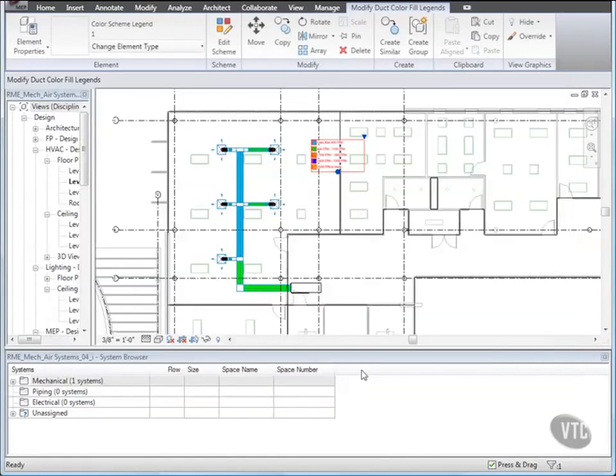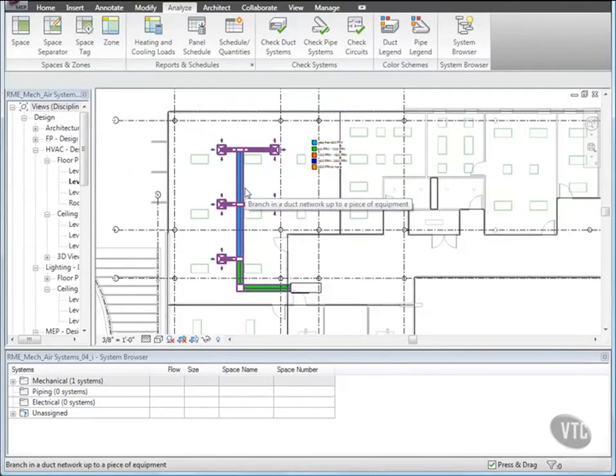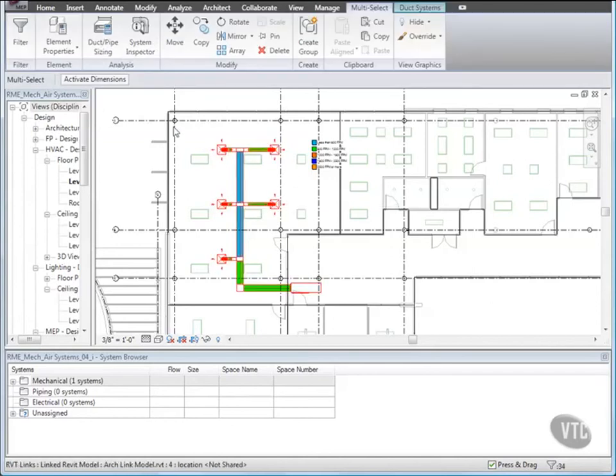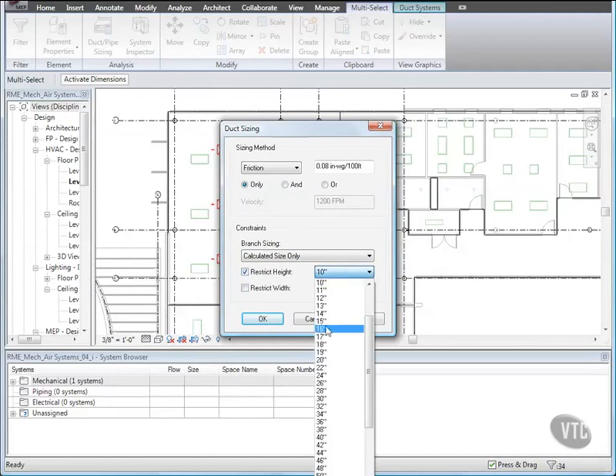Then from the Scheme panel, click Edit Scheme. In the Edit Color Scheme dialog, select Duct Color Fill Velocity. You can use this color scheme as a visual reference to confirm that air is flowing through the system ductwork at the appropriate velocity. Click OK and then clear the selection. Then place your cursor on a segment of the duct and press Tab three times to highlight the entire system, including the heat pump, and then click to select it. Then click Duct/Pipe Sizing. In the Duct Sizing dialog, under Sizing Method, with Friction selected, change the value to 0.08 in-wg per 100 feet, and then select Only. Under Constraints, for Branch Sizing, select Calculated Size Only. And then select Restrict Height and select 16 inches. Then click OK.